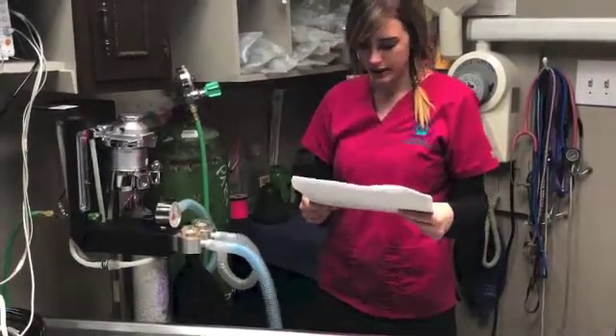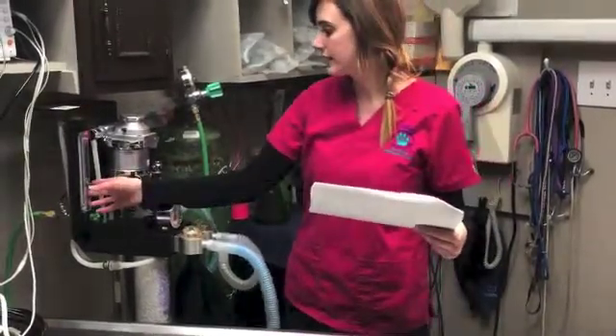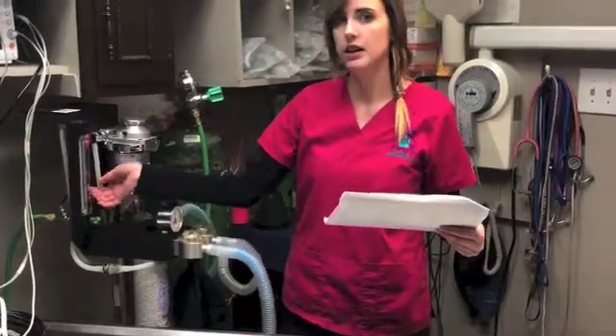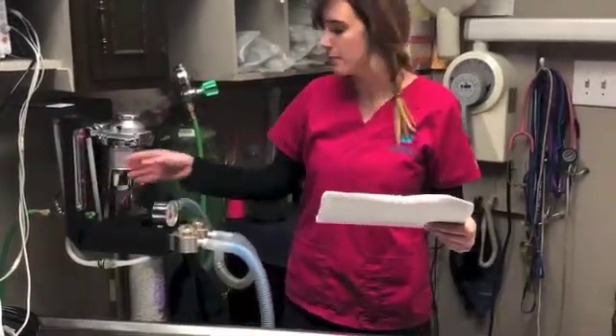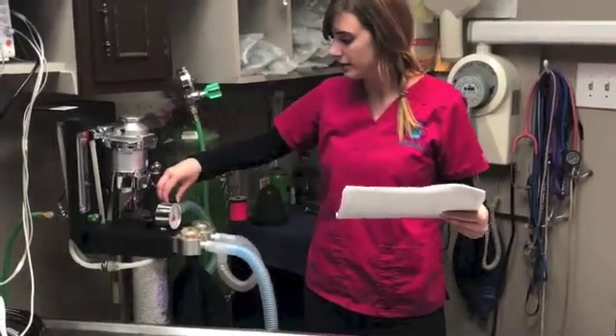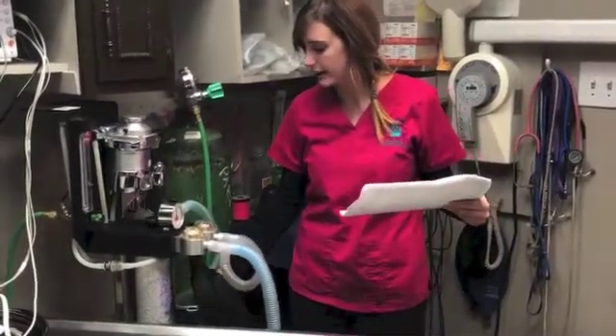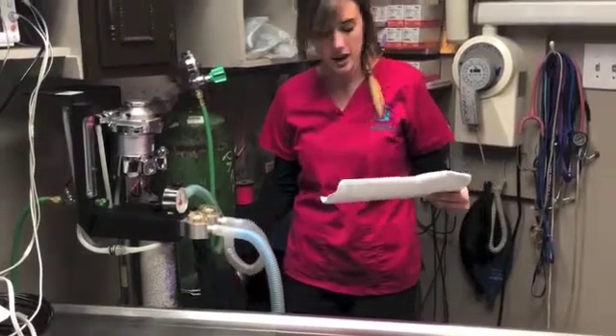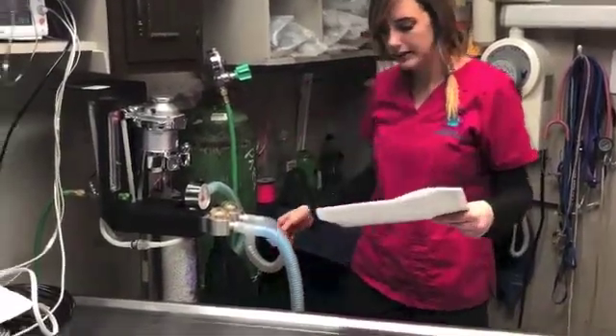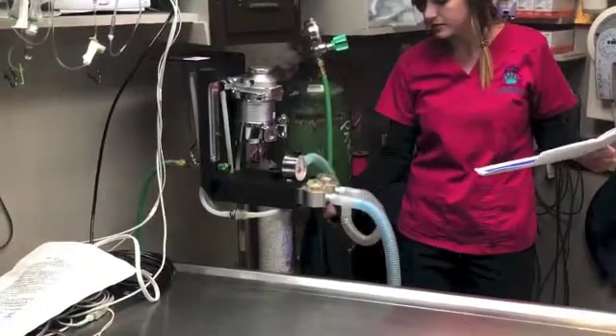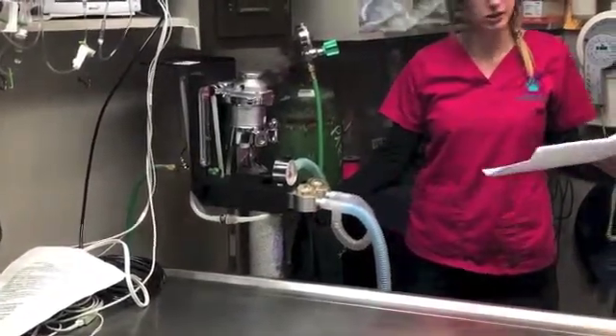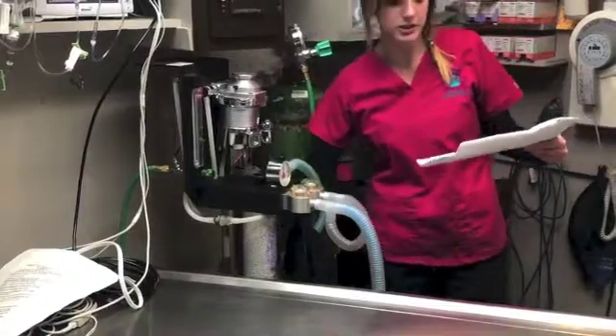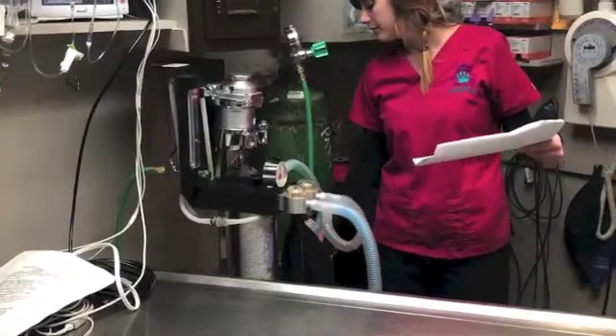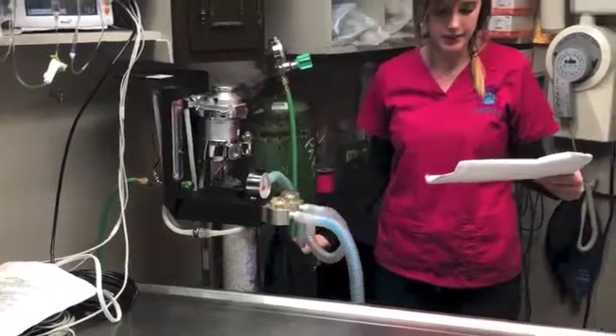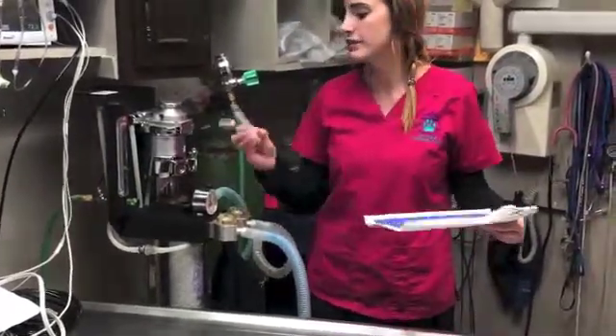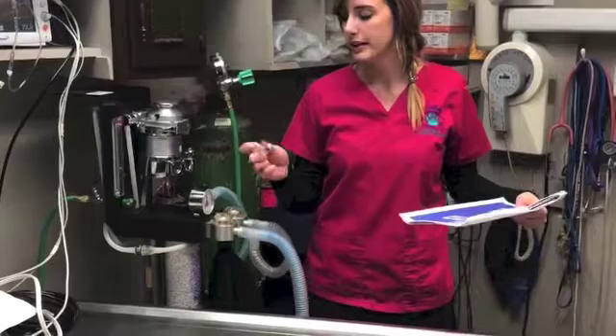So we have our oxygen flush valve right here, which would not be on a non-rebreather. And then we have our pop-off valve right here. This is to open and close. This can control this bag right here, and if you need to fill it up with oxygen. And then we have our soda lime canister, and it's a CO2 absorber, and when it turns purple, it's time for a change. And then we have our scavenger system, and that right there filters out the different types of gases. And then we always have our cuff syringe on hand to inflate or deflate the cuff.